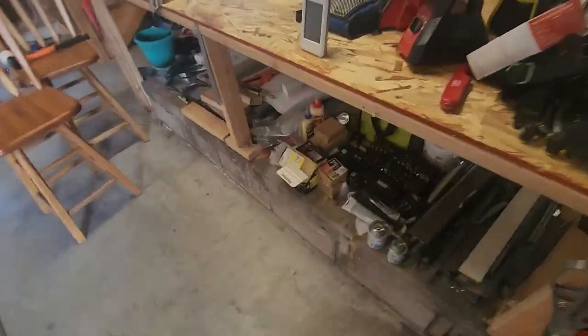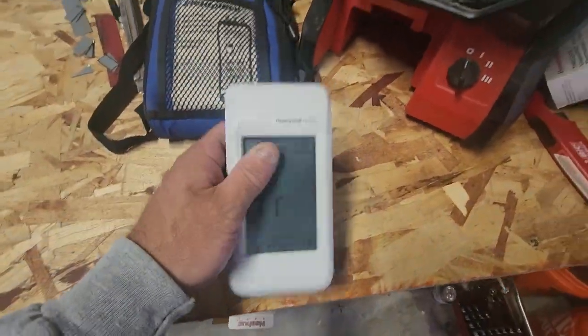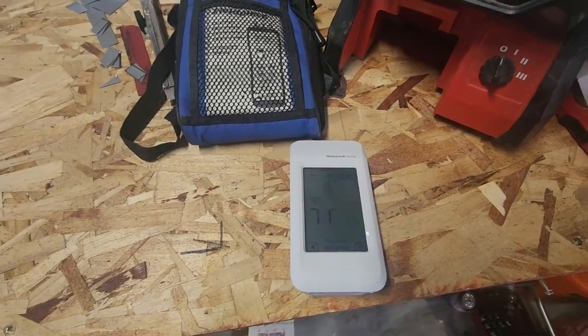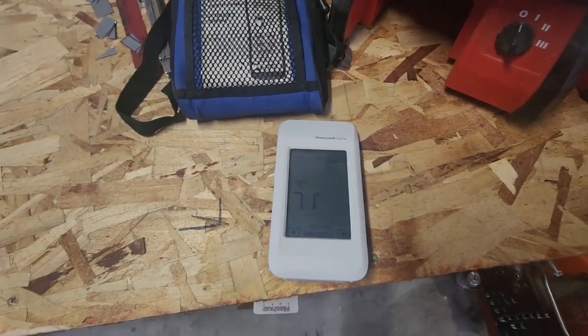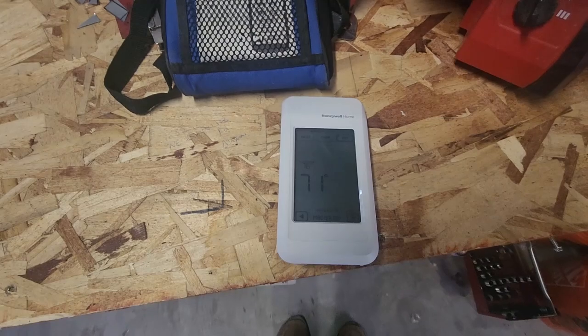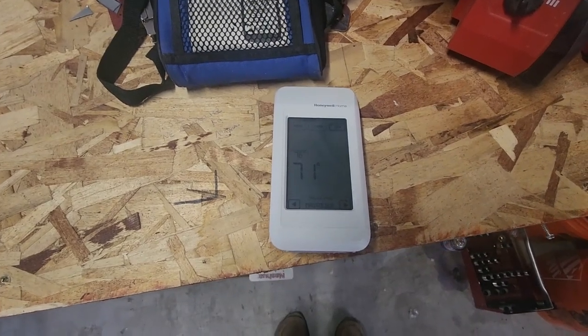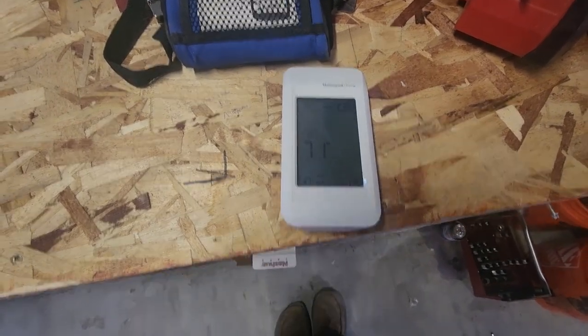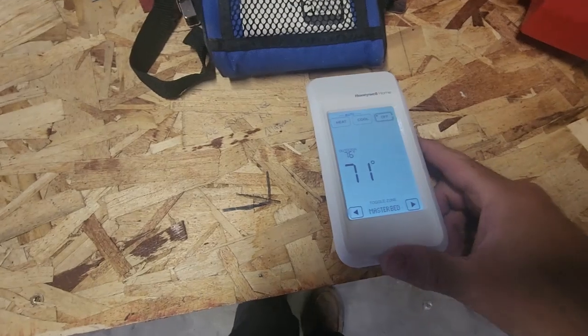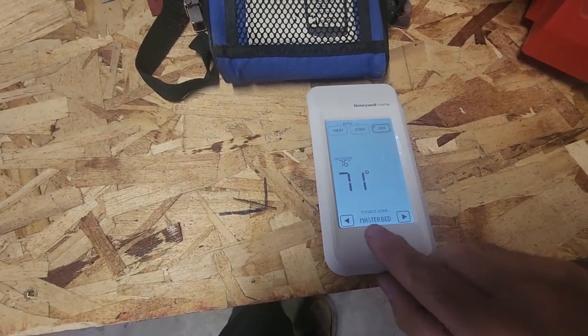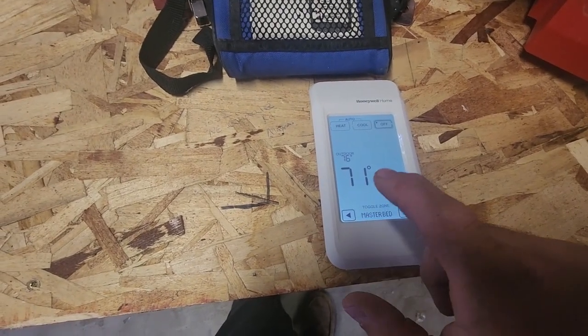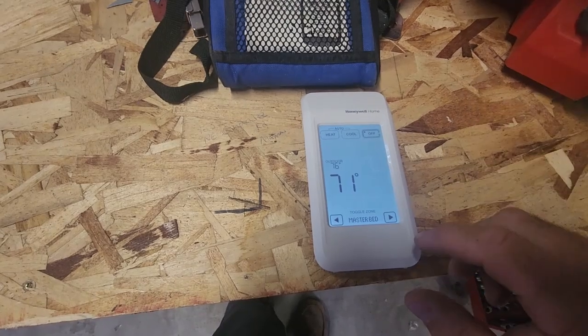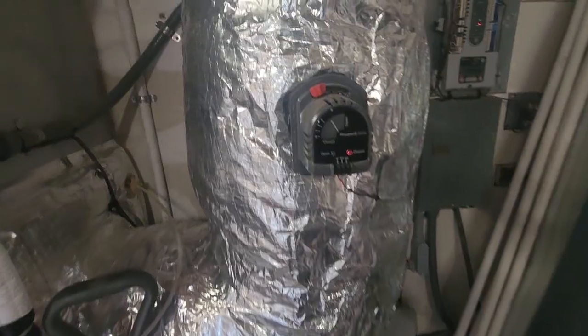Another thing that's beautiful is I have this portable comfort control here, and I can toggle between zones out here. I don't even have to go in the house. I wanted to do it by the zone panel, but it only stays in test mode for a few minutes, I'm realizing. So let's go ahead. Master bed, that's my downstairs. I'm going to flip that one on, and then turn the upstairs off, and let's see what that does to our static.